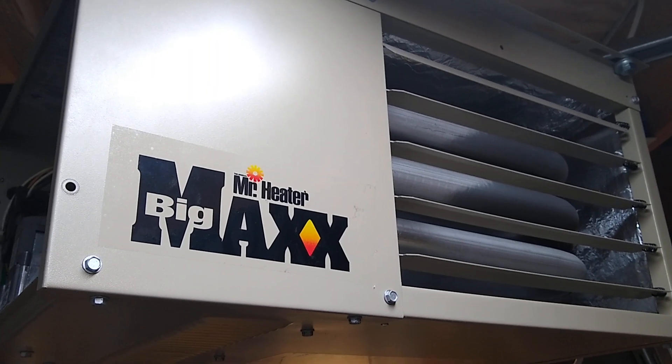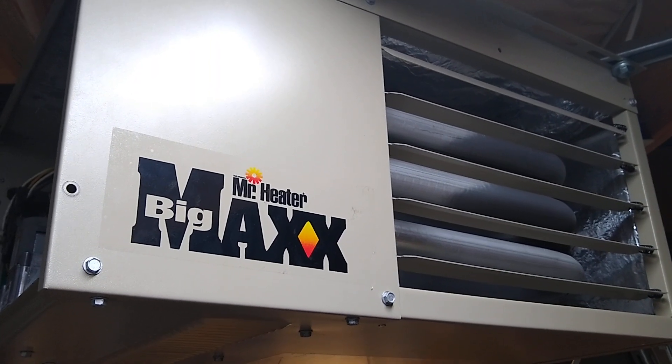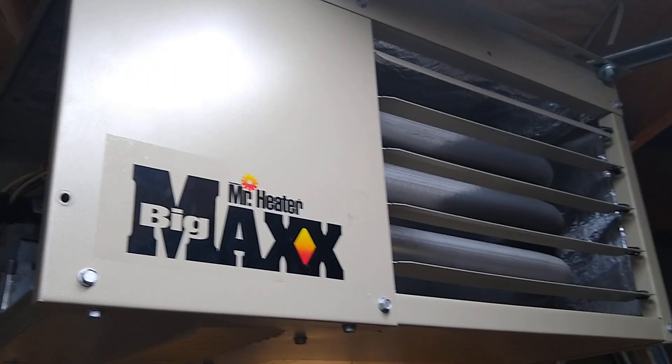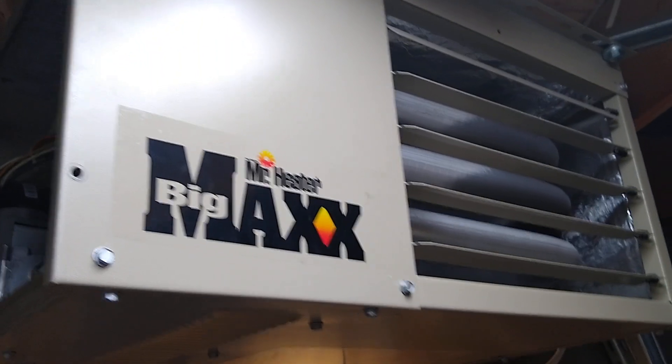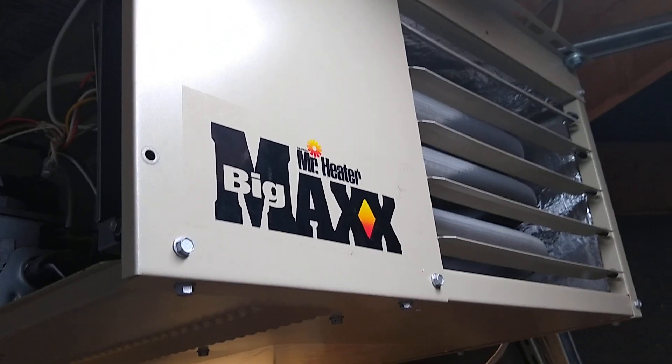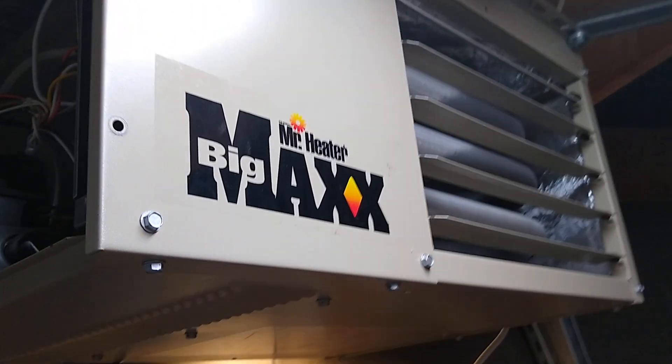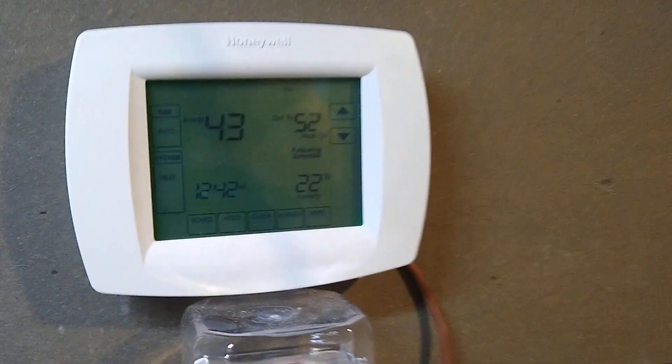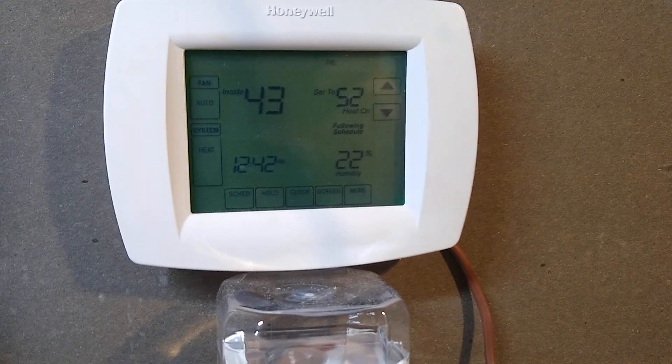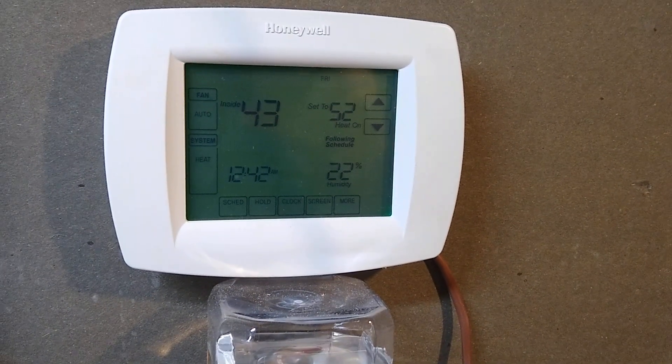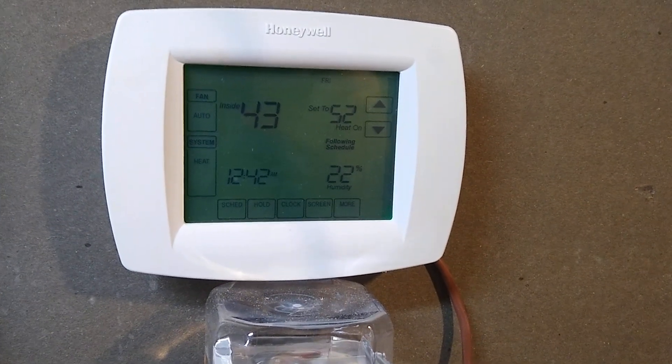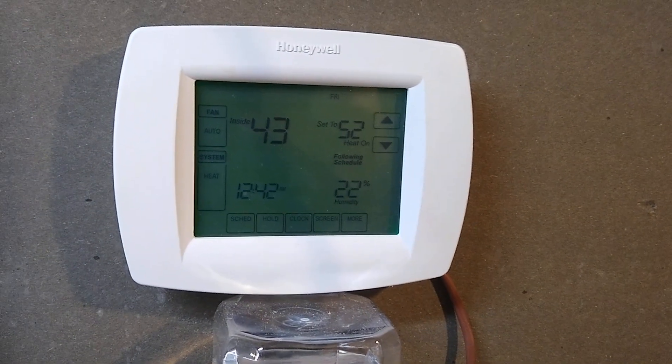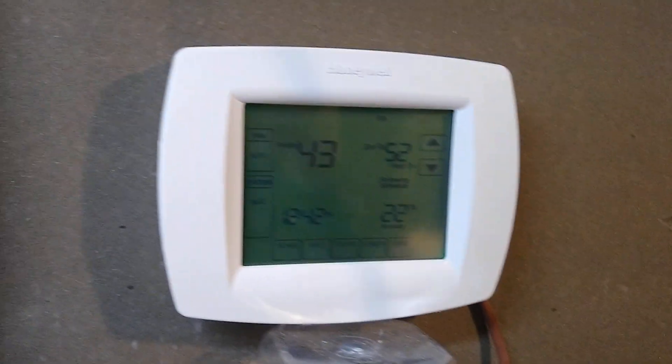So if you have one of these Big Maxx Mr. Heaters, particularly not on propane but on natural gas, you'll probably end up hitting this issue at some point, where your thermostat's calling for heat and the fan's running non-stop, but there's no heat.